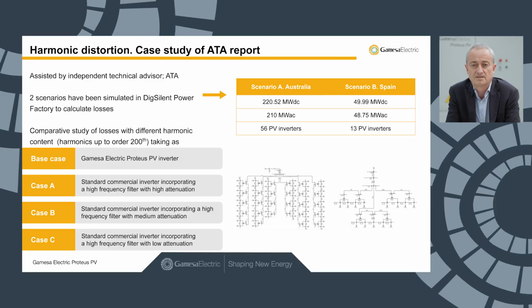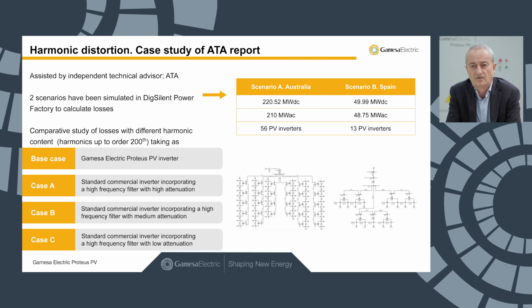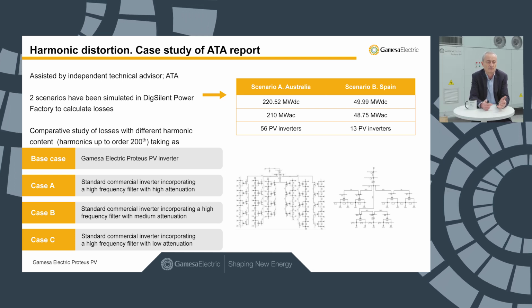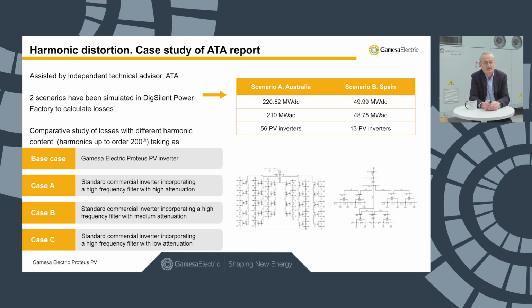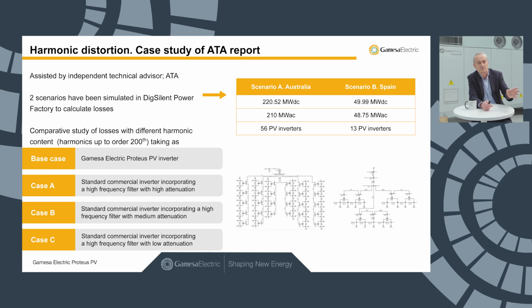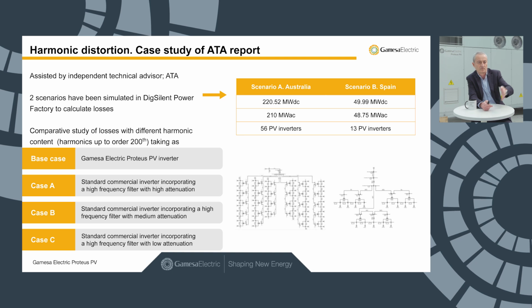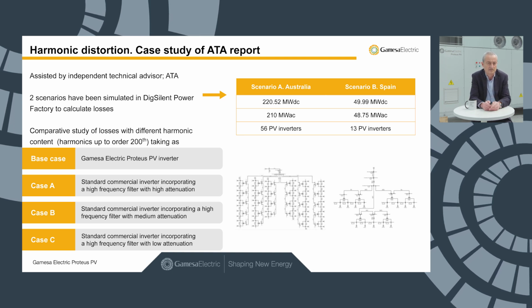Compared to other elements of the inverter, such as efficiency, which, as I said before, can be relatively easily simulated, harmonics is more complex. We need to run detailed simulations using very high-level simulation tools, such as PowerFactory and others. We requested the technical advisors to analyze two examples of power plants: a typical 50 megawatt plant in Spain, and a bigger one, as is the case in Australia, of around 200 megawatts. The technical advisor completely designed the plant, including not just the inverters but also the cabling, everything from the inverter to the point of interconnection, and simulated these power plants.